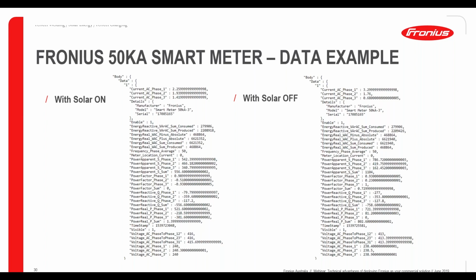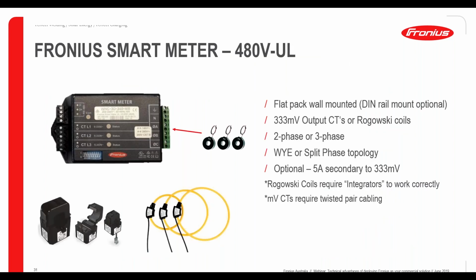If we go further, we have our second smart meter option, which is a 480V UL meter. What's different about this meter compared to the other one? It doesn't come with a display, but it does come with an option called 333 millivolt output CTs. These are typically a more cost-effective option than the 5A CTs, and because they present a voltage signal, burden and accuracy are not too big of an issue. Something to be cautious of: because this is a voltage signal, we have to use twisted pair for the CT wiring, otherwise there might be some noise induced.